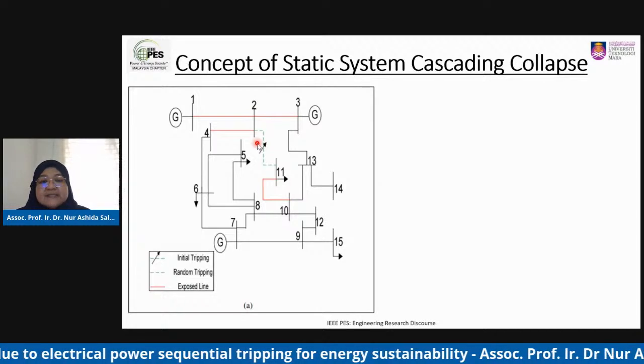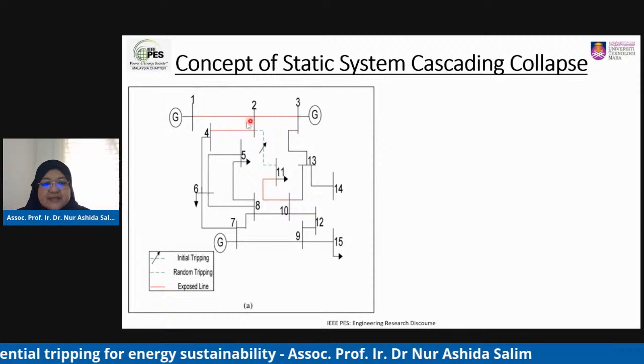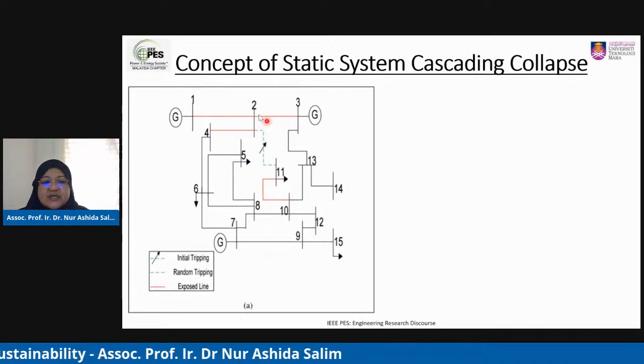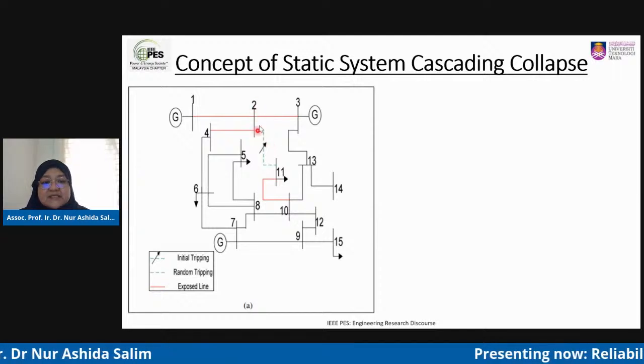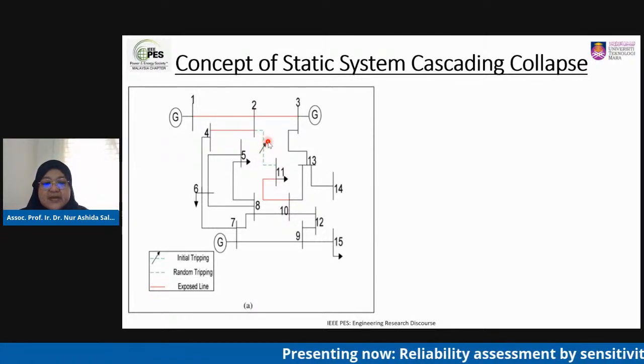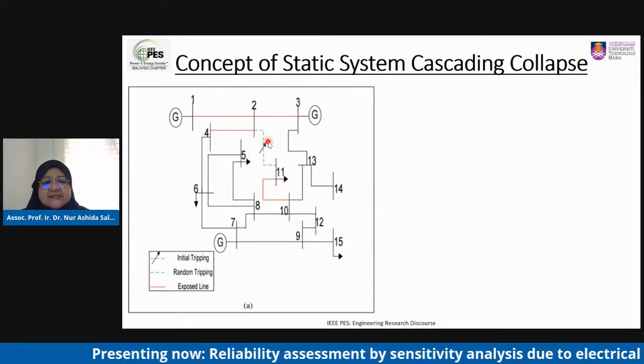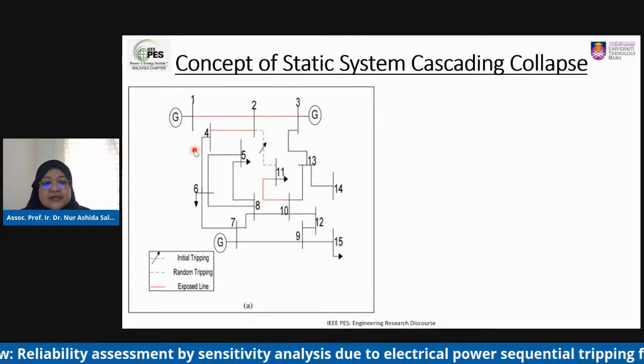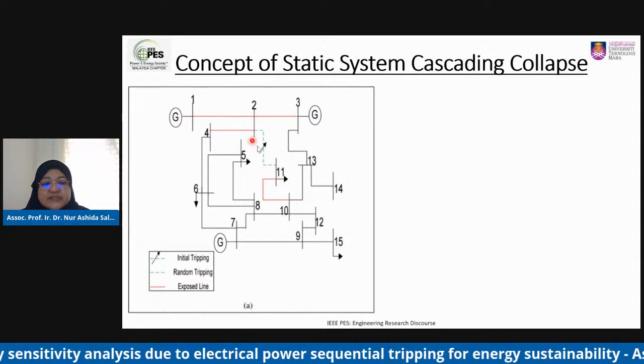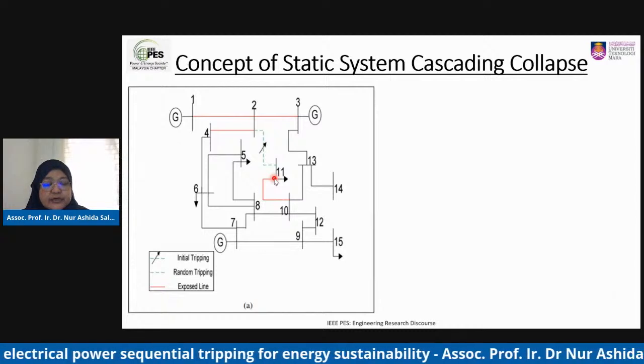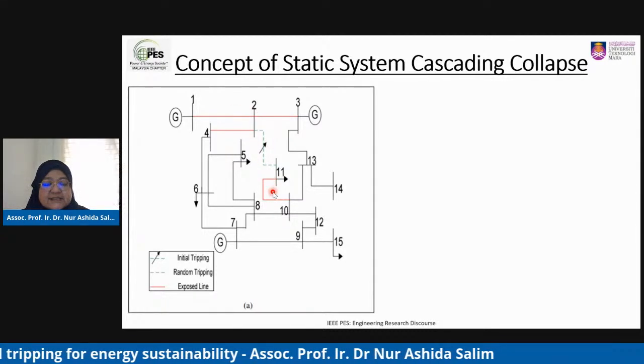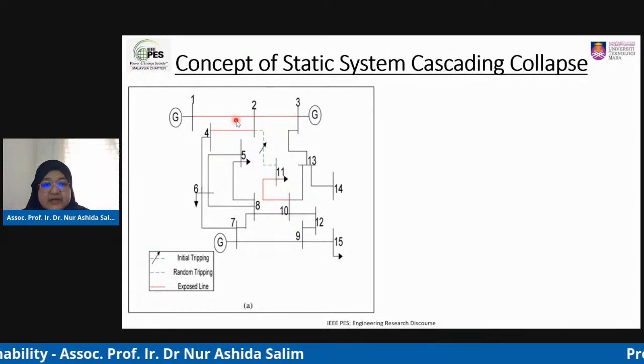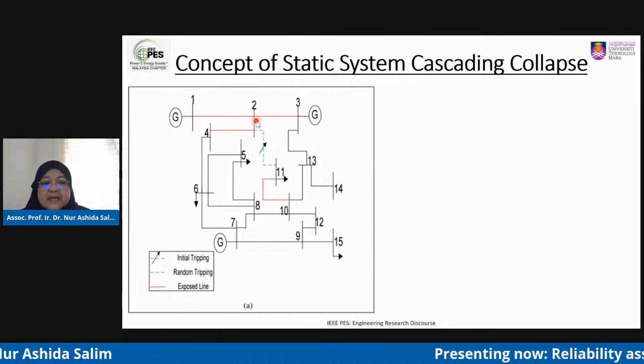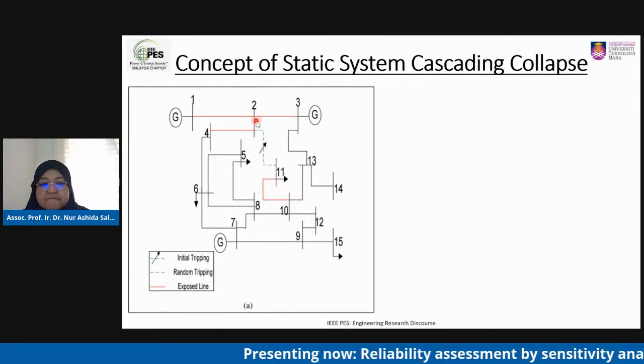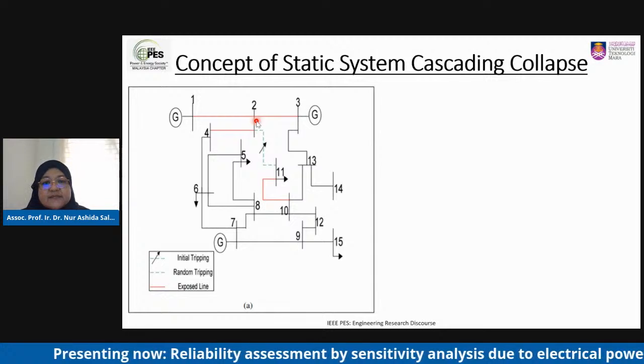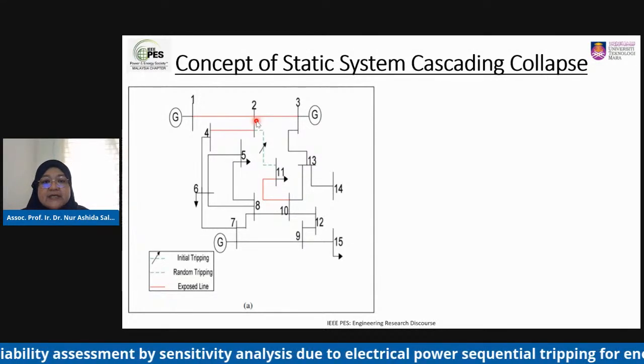So this is what static system cascading collapse looks like. The red lines are all the exposed transmission lines, which are all the transmission lines connected to the same bus as the initial tripping line. After this, we will perform a load flow study to see whether these exposed lines violate their thermal limit or not. If a particular exposed line violates the thermal limit, which is the MVA rating of that line, that exposed line will be the next line to trip. So the subsequent line to trip is based on the thermal rating of the particular line itself.